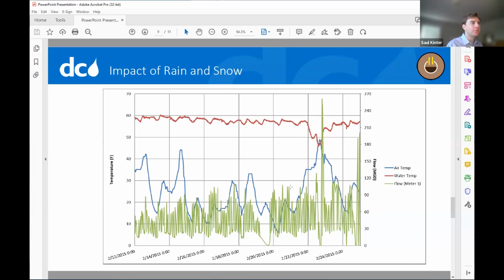Over the course of a week below freezing, we lost about 2 degrees. That's not nothing, but at the end of the day, if you're able to heat and cool out of a 56 or 58 degree reservoir, you're doing very well. You're doing a whole lot better than trying to heat or cool out of 10 degree Fahrenheit outside air. We had some snow on the ground in this period.